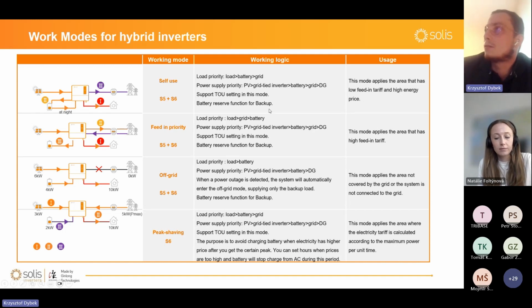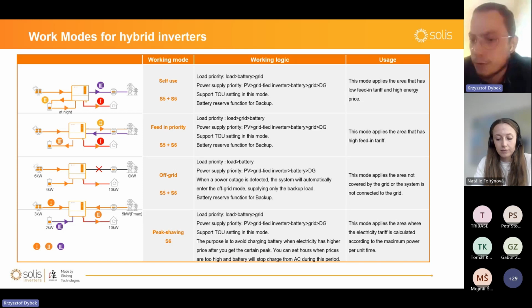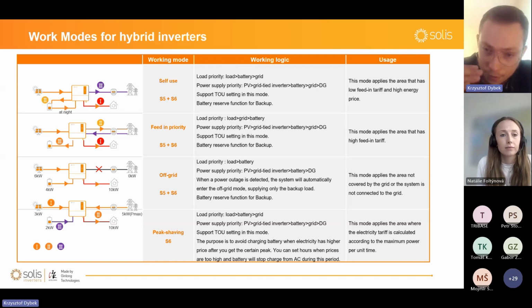And about the battery reserve function, this is for backup. So the battery has 3 settings regarding state of charge. First and the highest will be reserve SOC. So the battery will stop discharging to keep the remaining SOC, state of charge, for backup load if needed. If there is grid loss, the battery will drop down up to over discharge SOC and the whole system will be off. So below this point is just the self-use for battery and inverter. If it drops down, force charge SOC will cause auto charging of the battery up to over discharge SOC, and after that, of course, to backup reserve once again.